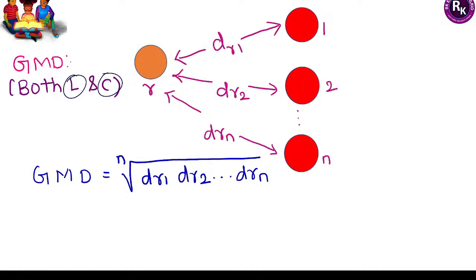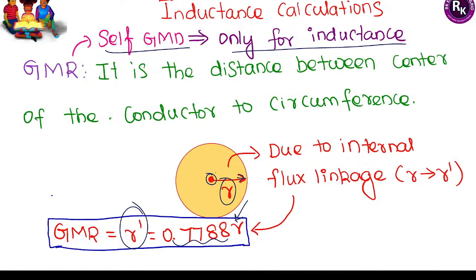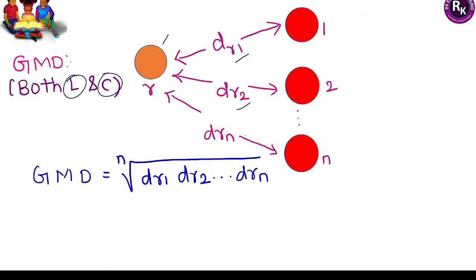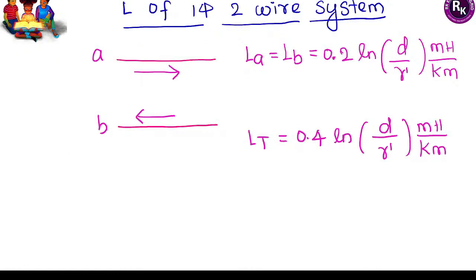GMD (Geometric Mean Distance) is used for both inductance and capacitance calculations. It refers to the actual distance between conductors in a bundle. Self-GMD refers to mutual distance within conductors of the same phase, whereas mutual GMD is the distance between conductors of different phases. The formula for GMD is the n-th root of the product of all inter-conductor distances — for three conductors, it is the cube root of the product of three distances.